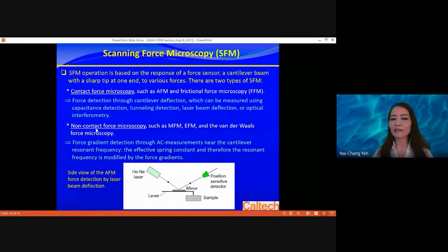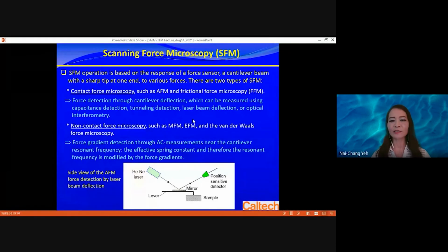Or you can have a non-contact mode to detect a gradient of the force. There are different ways of detecting the amount of deflection. The most typical ones are capacitance detection, tunneling detection, laser beam deflection, or optical interferometry. I will only mention the most typical one, laser beam deflection.